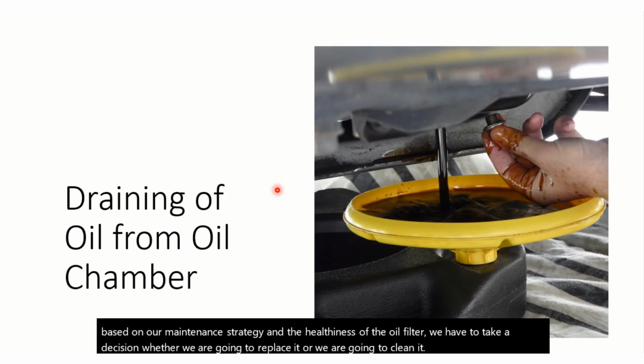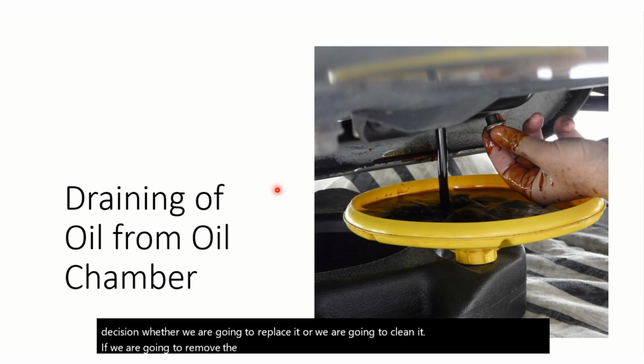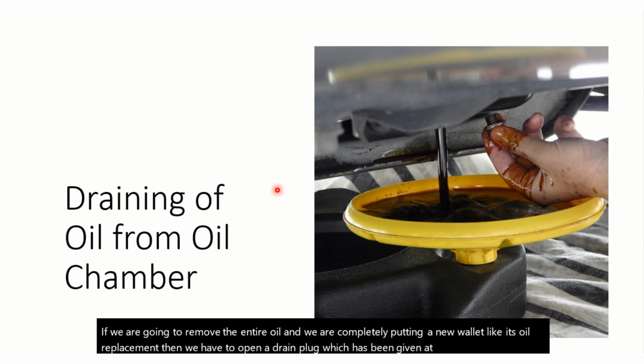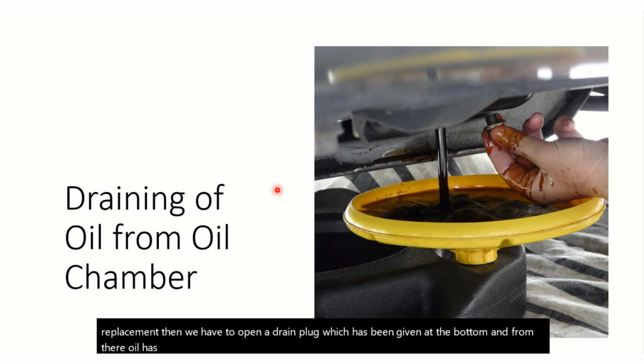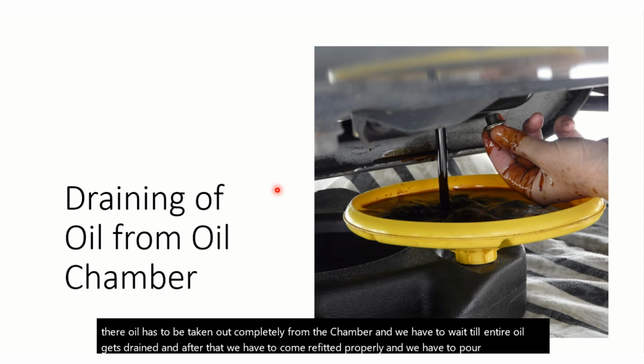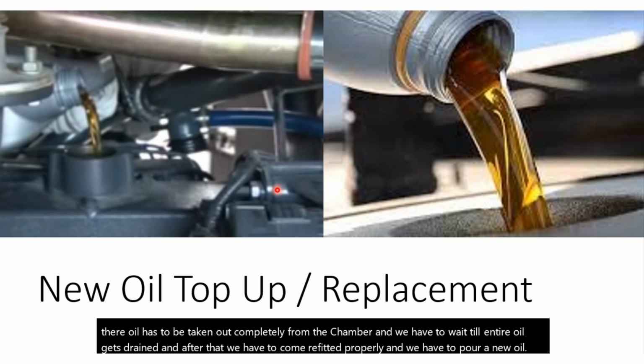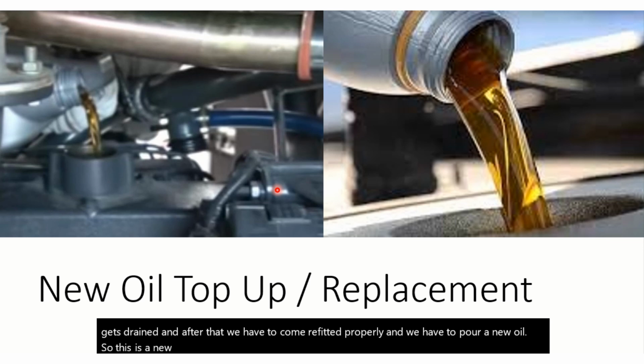If we are going to remove the entire oil and completely put in new oil, like an oil replacement, then we have to open the drain plug which is given at the bottom, and from there the oil has to be taken out completely from the chamber. We have to wait till the entire oil gets drained, and after that we have to refit it properly and pour new oil. So this is the new oil top up. If it's 250 hours or half a year or so, we can replace the oil based on our requirement.